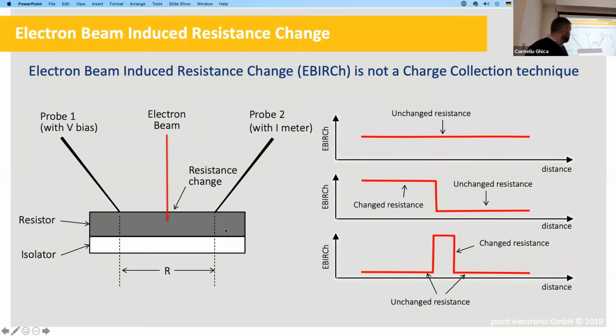What is the principle of operation? Again, we have two probes, and we have a resistor, let's say, and it's an insulator, so we separate ourselves from the rest of the microscope electronics. But this time we will not rely on the absorbed current or on splitting the absorbed current as we did for RCI. This time we will force a voltage between these two probes. So we will force a current through the device. And we can control a bias, a voltage bias, and we can control the amount of current that we force through it. And in this technique, we will use the electron beam as a way of changing local resistance.